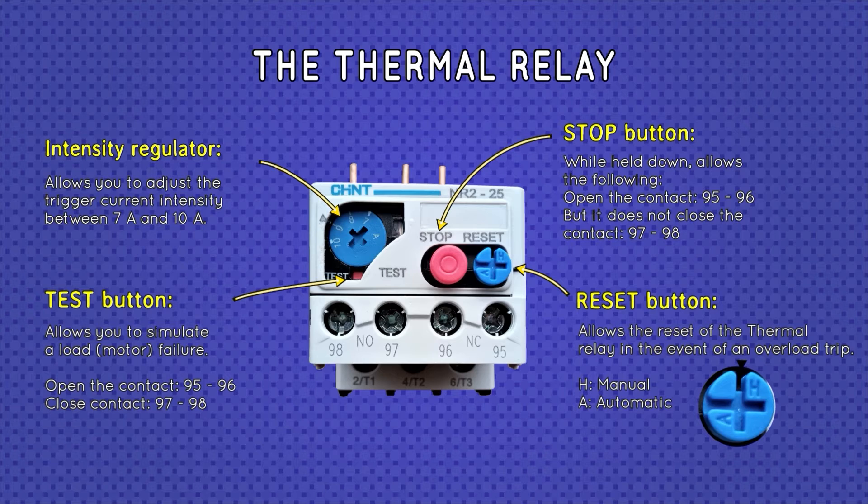The stop button allows the engine to be stopped, that is, it opens contact 95, 96 but does not close contact 97, 98 since this should only be closed to indicate a fault or alert about a problem in the engine. So, this is all we can find in a thermal relay.